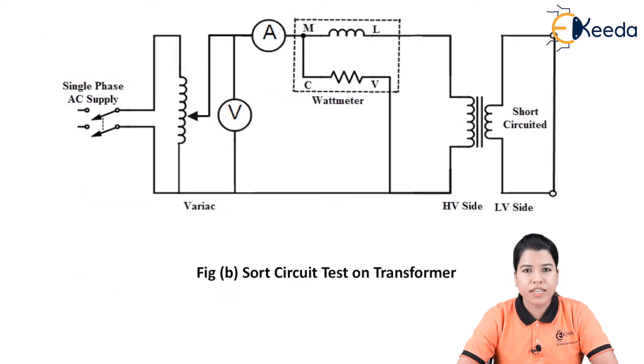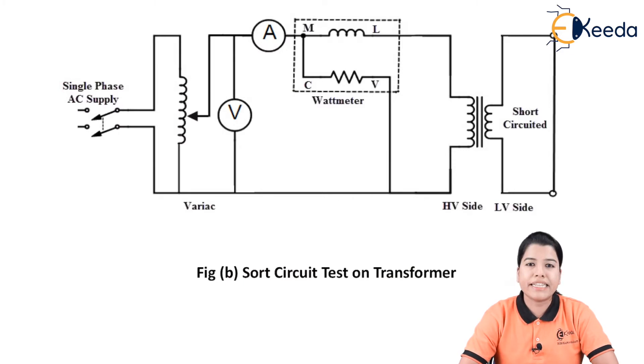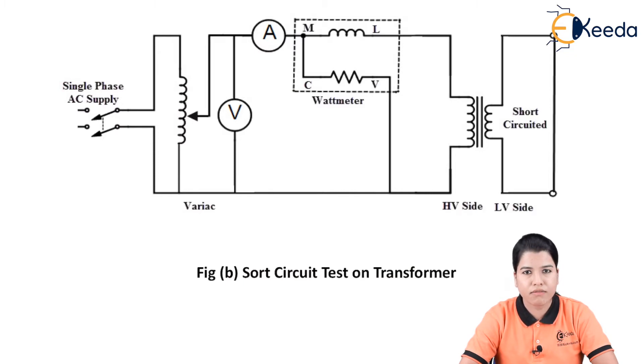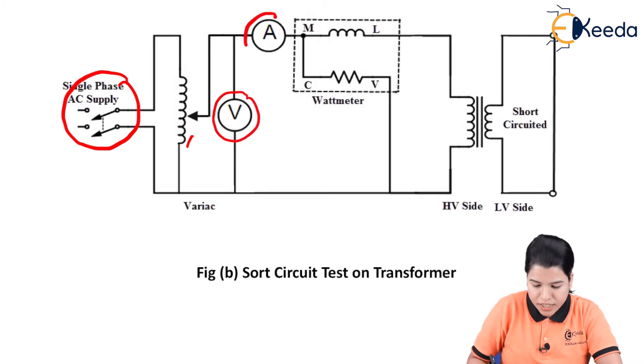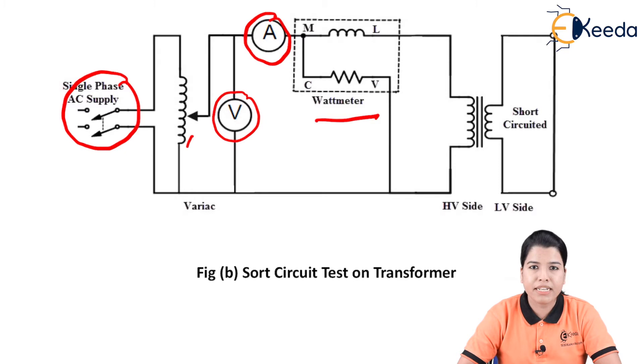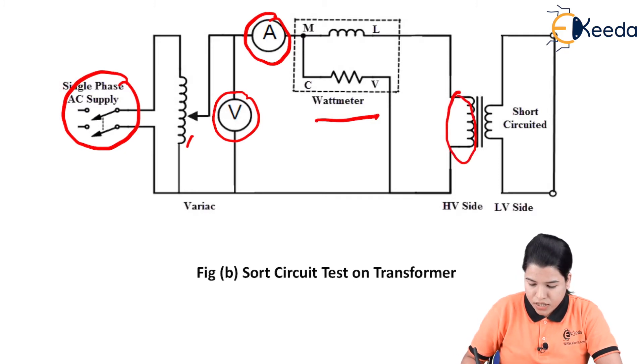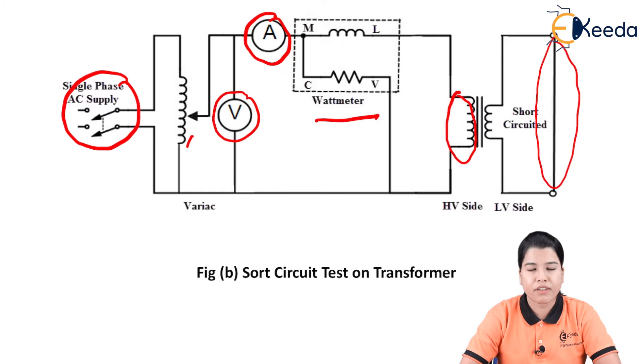Now let us study the short circuit test. The short circuit test is done to determine the copper losses as well as equivalent parameters of the equivalent circuit. In this test, the supply is given to the HV winding, whereas the LV winding is short circuited using a thick copper wire. The circuit includes a variac, a voltmeter, an ammeter, and a wattmeter with terminals M, L, C, V connected to the HV winding.